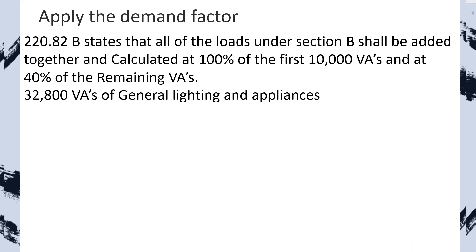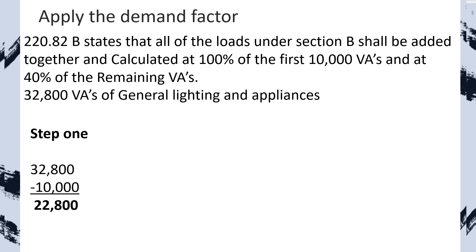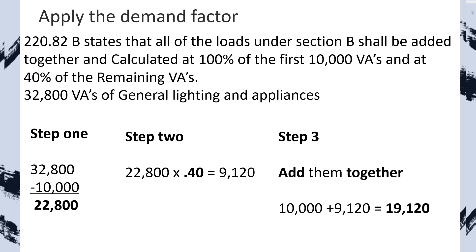Now that we've learned to take our three VAs per square foot and our 4,500 and then the nameplate of all appliances, let's learn how to apply the demand factor. It's super simple — total all that up and apply one general demand factor. Using an imaginary load of 32,800 VAs of general lighting and appliances: step one, take the first 10,000 at 100% and set it aside; take the remainder at 40%; then add back the 10,000, and we end up with 19,120 VAs. Then all we have to do is calculate the HVAC.